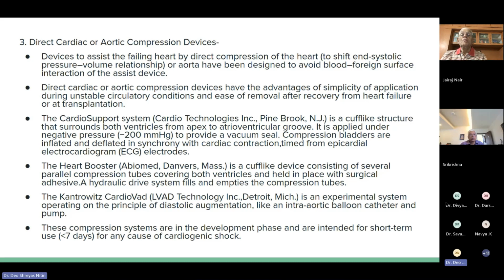It is applied under negative pressure of minus 200 mmHg to provide a vacuum seal. Compression bladders are inflated and deflated in synchrony with cardiac contraction timed from epicardial electrocardiogram electrodes. The heart booster is a cuff-like device consisting of several parallel compression tubes covering both ventricles and held in place with a surgical adhesive. A hydraulic drive system fills and empties the compression tubes.